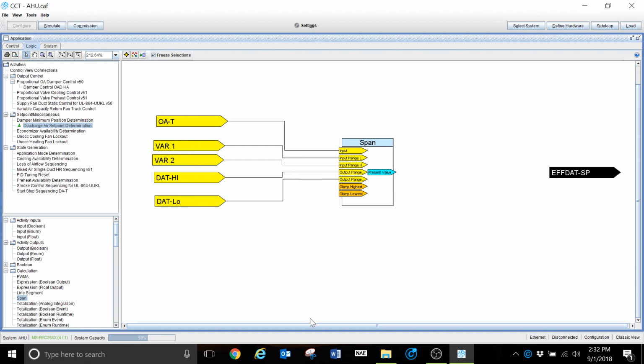It's a little bit confusing until you actually get into it and see how these span blocks work. Once you do that, it's easy to determine which way you need to go. I have set these up before and they would be the exact opposite of what I needed, so I would just swap those and be good to go and back in operation.